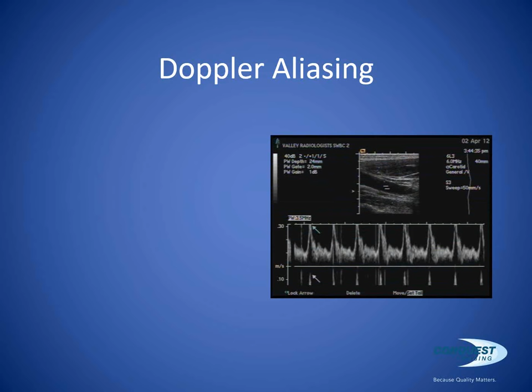I've received countless calls over the years that my Doppler is defective. It is reading inaccurate frequencies. It's showing me pathology where there is no pathology, and there's something called aliasing. When an ultrasound system is not set up properly, the ultrasound signal will do something called wraparound, and it occurs when the velocity of the blood exceeds the system's ability to display it. Can this be remedied by a scale or PRF adjustment?